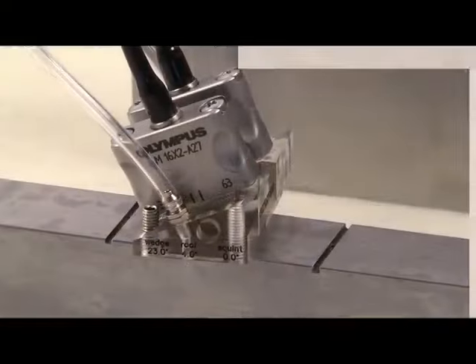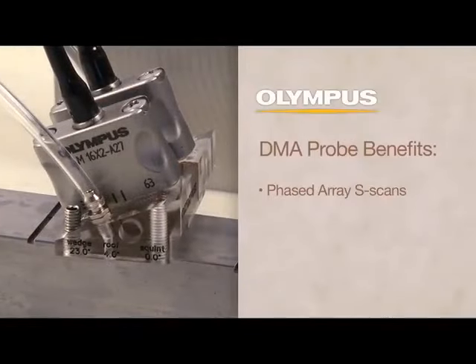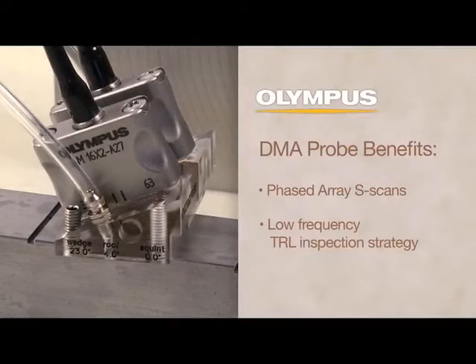Detection and sizing of difficult-to-penetrate materials is improved by combining the benefits of phased array S-scans and low-frequency transmit-receive or TRL inspection strategy.